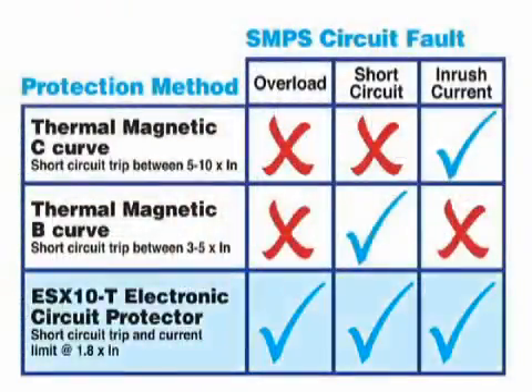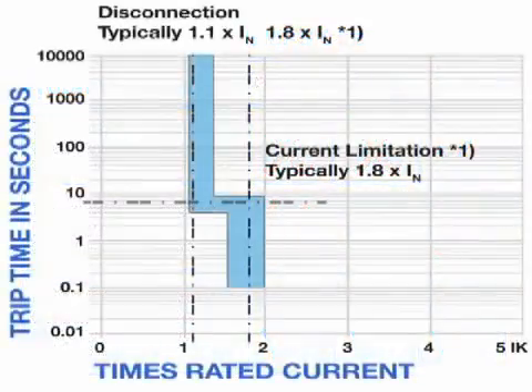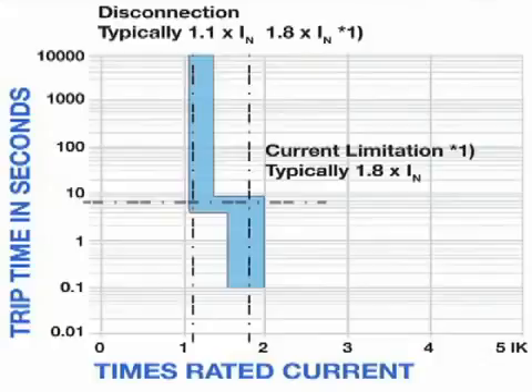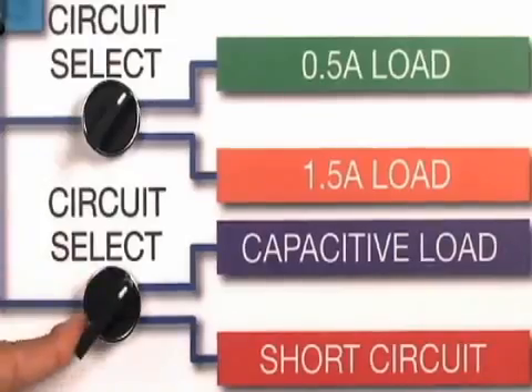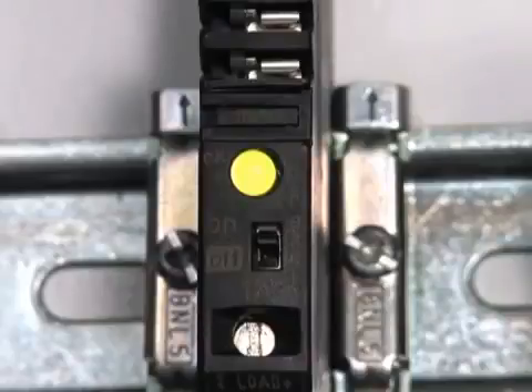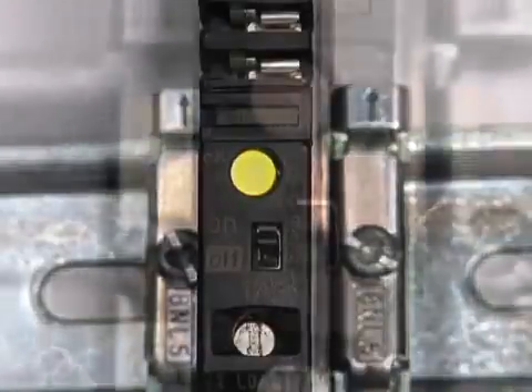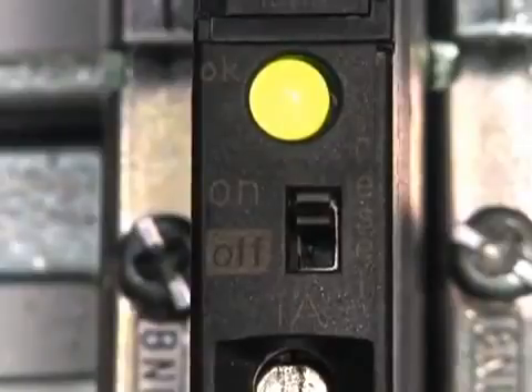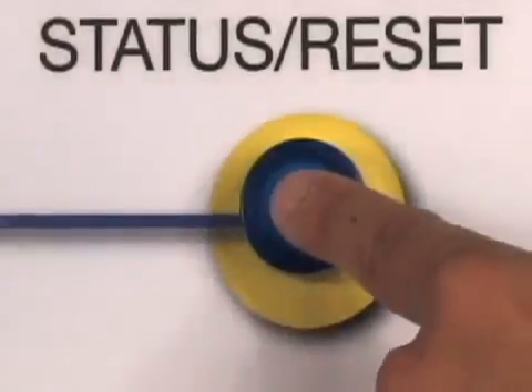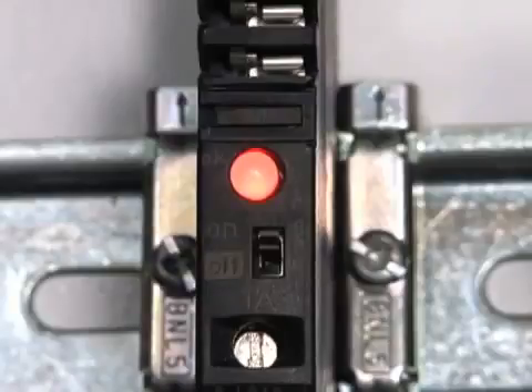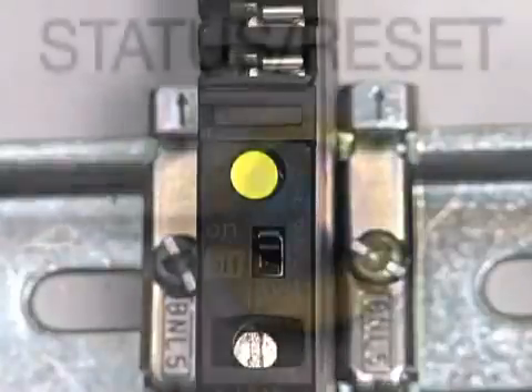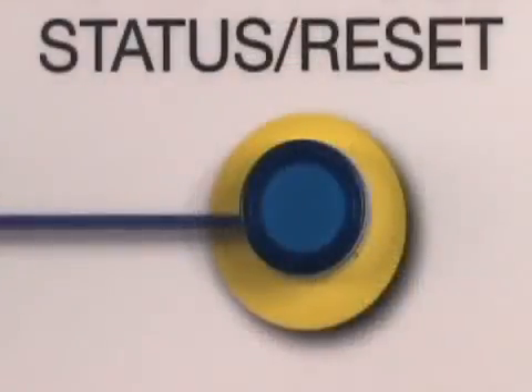Finally, the ESX10T, because it's a current-limiting device, stops the inrush current at 1.8 times the rating for up to 5 seconds. Because most inrush currents last below a second, the ESX10T is able to limit the extra current and avoid premature tripping. When an overcurrent condition occurs, this device is reset either by actuating the on-off switch located on the device or by remote reset at a discrete or group level. Remote reset can be performed by a low voltage signal to the device. This is a significant advantage in certain environments where access to control cabinets might be restricted.